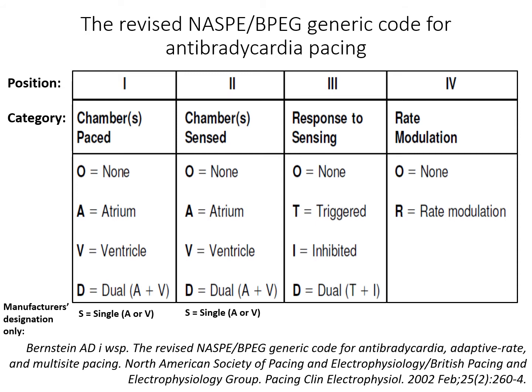The letter markings of individual types of cardiac pacemakers presented on the previous slide are associated with the basic modes of their action. However, as you can guess, each of them can be reprogrammed to work in a different way, but not in any mode, with the exception of dual-chamber cardiac pacemakers, which have the largest possible number of modes among cardiac pacemakers.